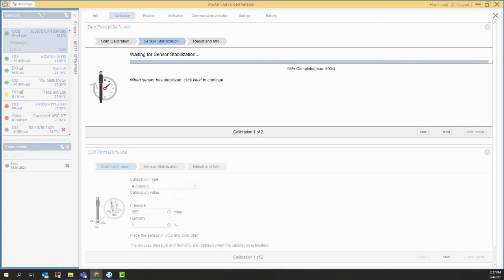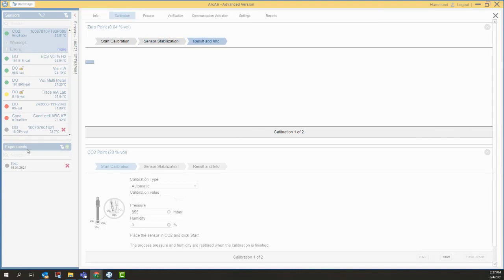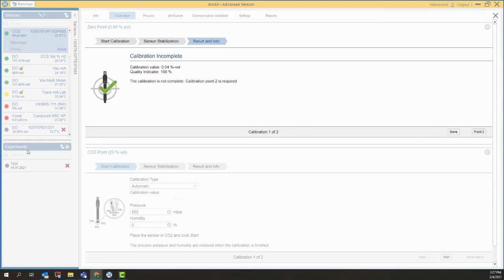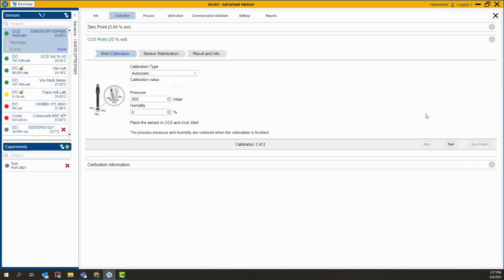Okay, so my air calibration is just finishing up here. As it completes here, you will get a note that it's passed calibration, but it says calibration incomplete. And there's a note here that says calibration point 2 is required. So this is part of the 2 point calibration that's required. So I'm going to say done, and I can go down and go to my second calibration point.